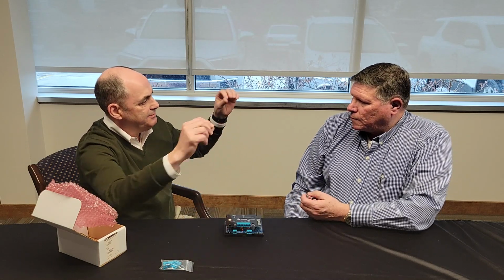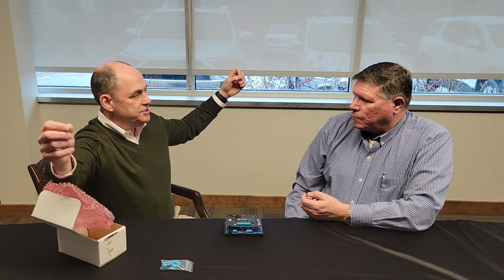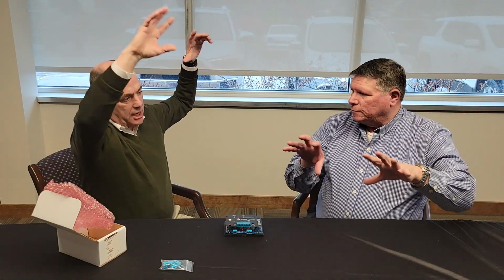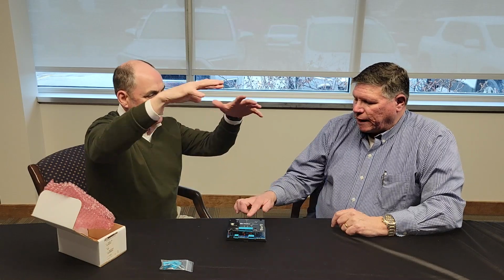Exactly. So where is the actual detection done on this? Yeah, so traditionally we use 2 types of sensors. We use a fiber optic sensor, which in a larger piece of switchgear you can wind around the bus bar and wind it all the way through the enclosure. Yep. And then the other sensor we have is more of a dome sensor. So it's a little bit of a point light sensor. And that connects into one of these connectors. So we can handle 2. So this one does not work with the fiber optic, only with the point sensors.